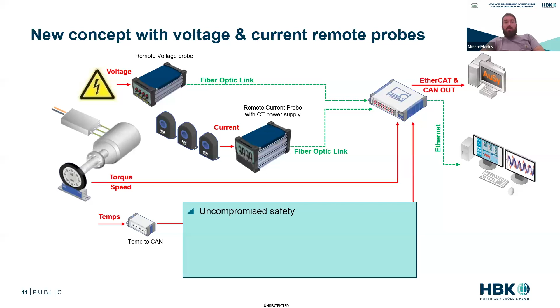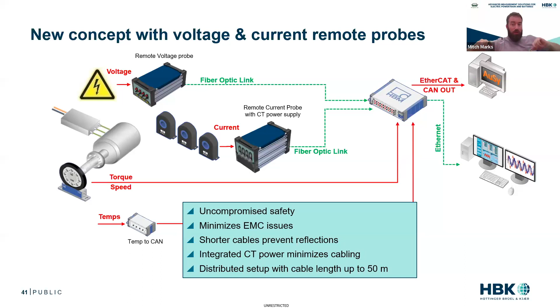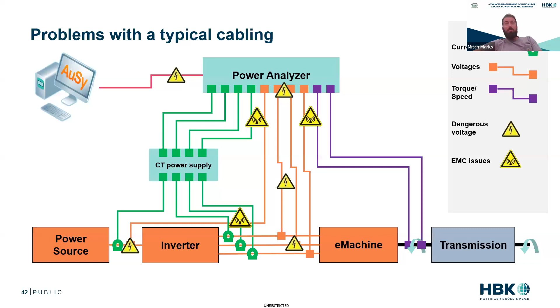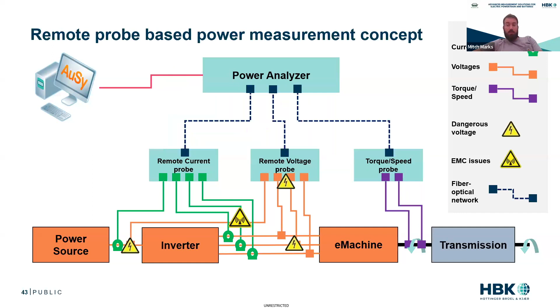What does the fiber optic probe do for us? It eliminates safety issues of those high voltages—you have no high voltages coming back to the measurement system. It minimizes EMC because we've turned our inductance and capacitance to zero. Shorter cables prevent reflections, allowing us to go to higher sampling rates. Integrated CT power minimizes cabling, so there's a lower chance for loops and EMC/EMI issues. And lastly, we can distribute these probes at a very large distance—put them all over the control room or test lab to reduce the noise you pick up. So we go from all these EMC, EMI issues and multiple cabling routes to a really clean setup with very short cables, very short distances, very low interaction, coming back fiber optically to the measurement system.